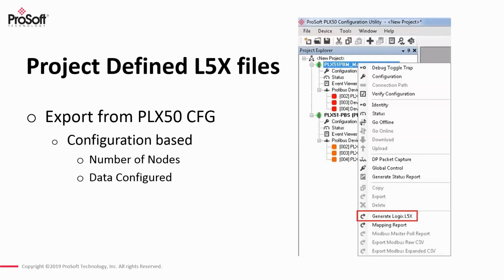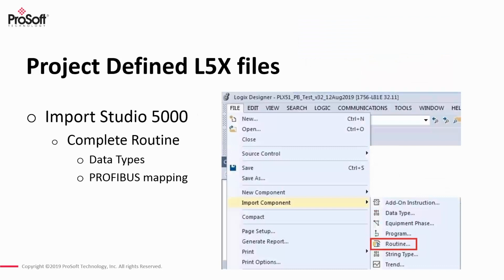You can then go ahead and export a custom L5X file from this configuration utility, and it's going to automatically bring in the number of nodes that you've got on the network and the amount of data that's configured for each one of those nodes, and build out your UDTs and ladder logic to go ahead and copy that information over for you. So this is done using an import component function within the Studio 5000 software, or Logix Designer, Studio 5000 Logix Designer software.